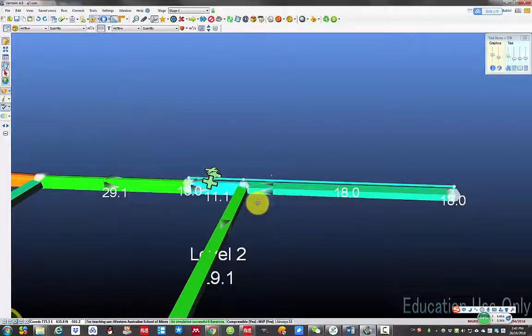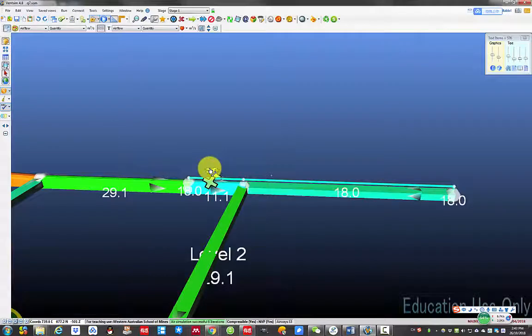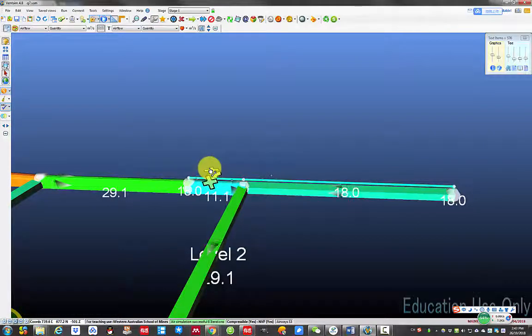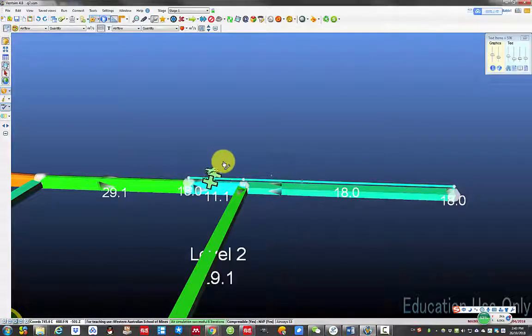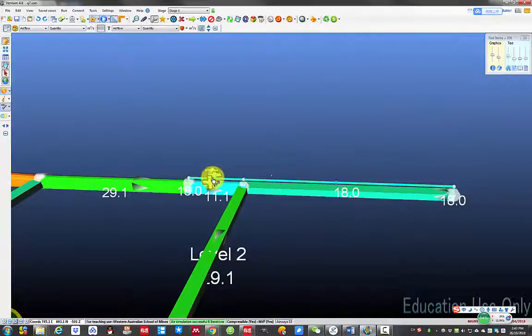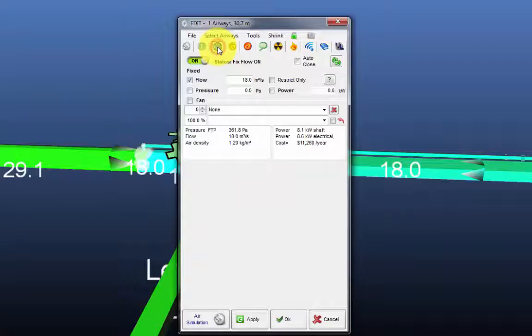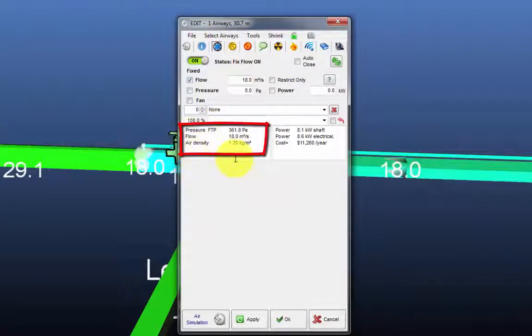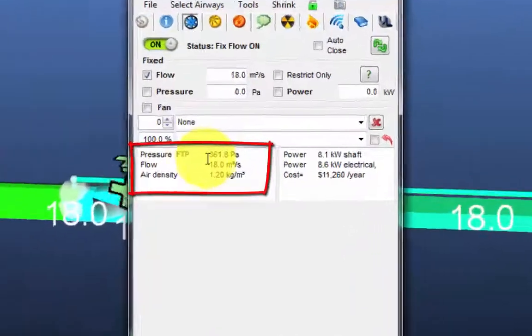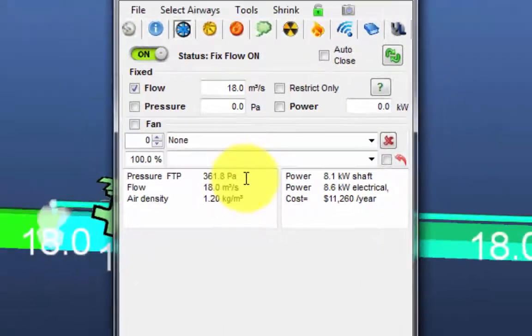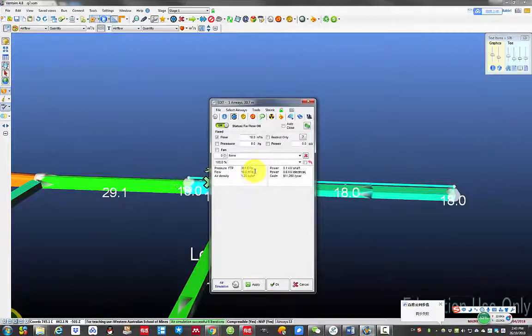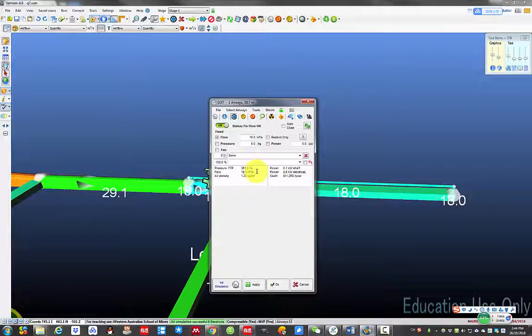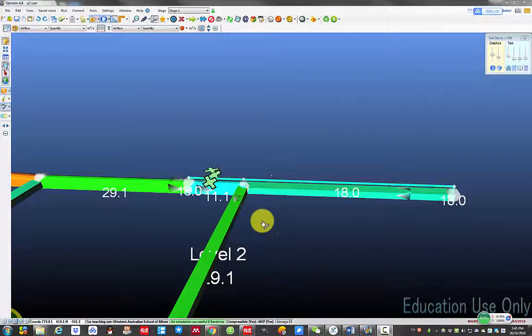Until now, we have only manually put a fixed flow on the duct, but we need to select a proper fan based on the simulation results. The required fan operation condition can be found here. Click edit, click the little fan and click this fan icon and here are the fan operating point. So the fan total pressure is 361 Pascal and the flow quantity is 18 cubic meter per second. Based on this information, we can select a proper fan and install it here. I will demonstrate how to put a fan in the simulation in a different video.